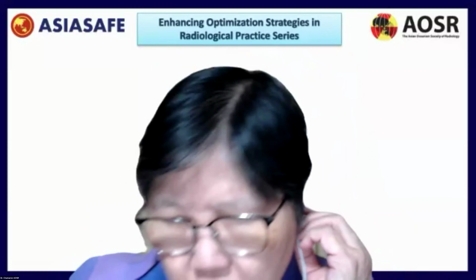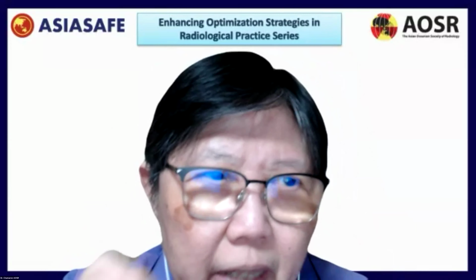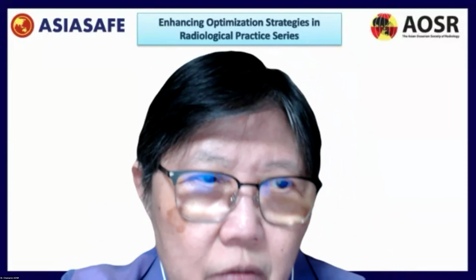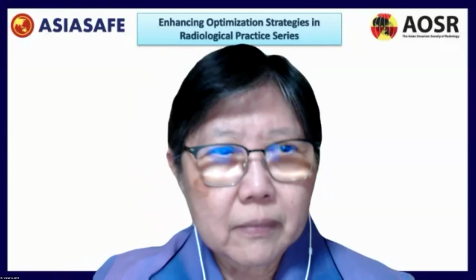Thank you so much. So Sam, correct me if I'm wrong. You mean that the DI value is already in the DICOM tag, so you can pick that on the screen when you have your PACS team display that particular value, right? Yes. The EI and DI value should be listed in the DICOM header. So if you don't see it on your screen because of your hanging protocol, you should be able to request it.